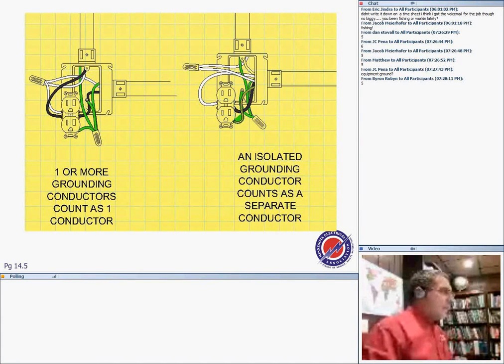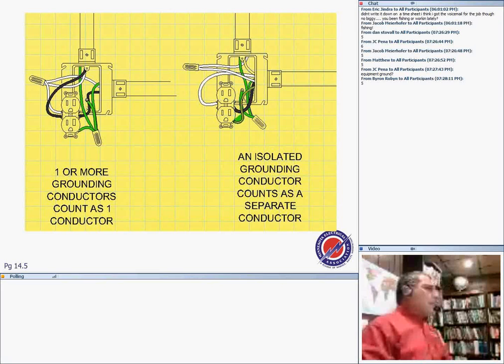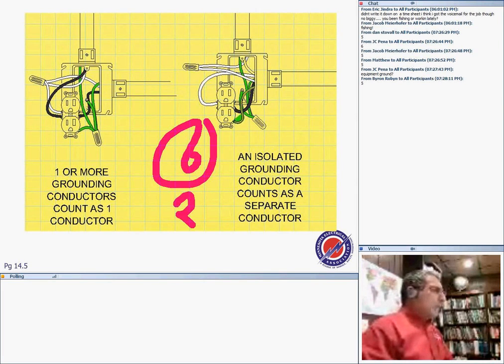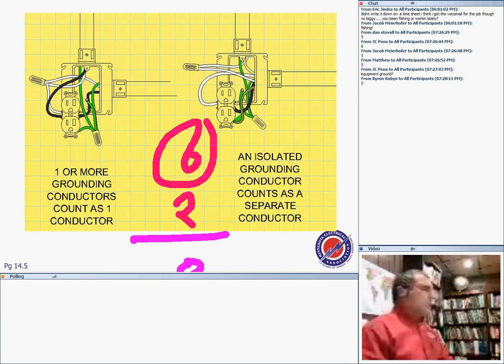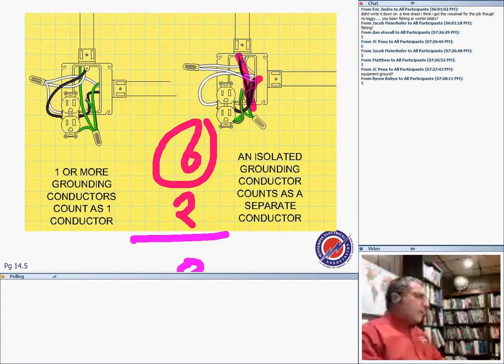So there are grounds coming in, 2 grounding conductors. If it's only grounded through conduit, or if there are 2 grounding conductors coming in, you count only one of them, and you count 1. So that will be a 6 conductor box, plus 2 for the device. That will get you an 8 conductor box. Any questions about that? Thank you for correcting me. Grounding conductors will count, and if there are 2 of them, they count as 1.